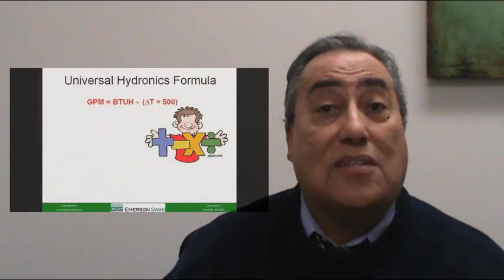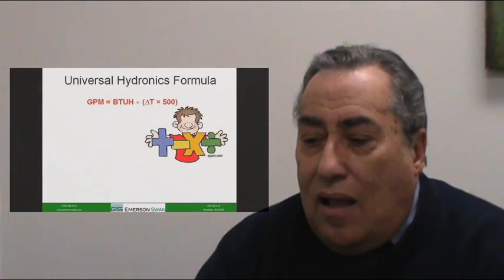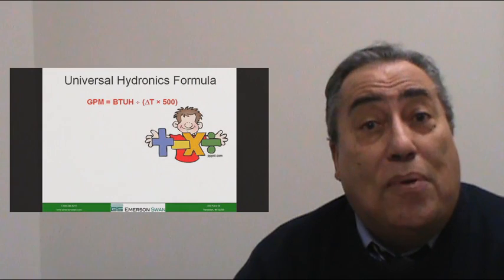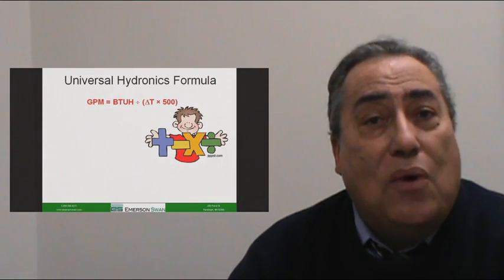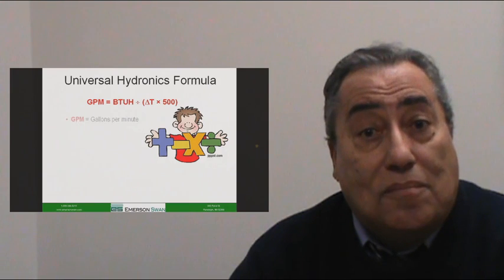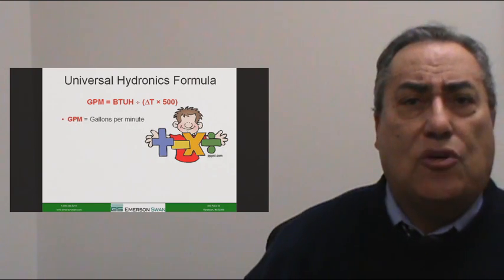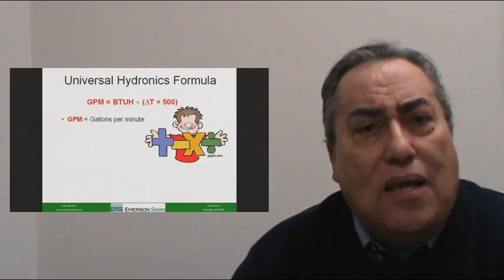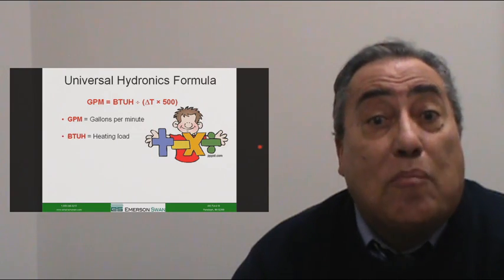Let's take a look at this formula and see what it's all about. The formula is simply this: GPM equals BTUH divided by Delta T times 500. Let's define these terms, starting with GPM—very simple, gallons per minute.